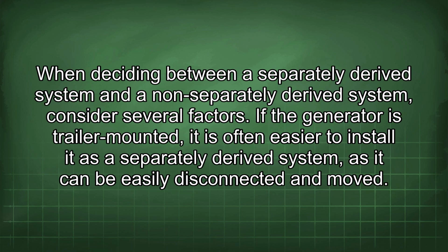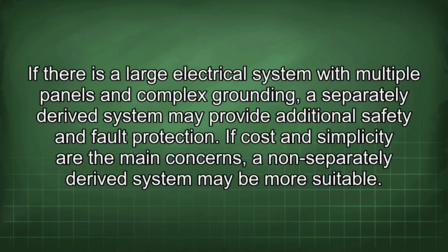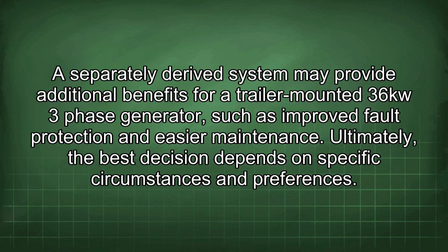When deciding between a separately derived system and a non-separately derived system, consider several factors. If the generator is trailer-mounted, it is often easier to install it as a separately derived system, as it can be easily disconnected and moved. If there is a large electrical system with multiple panels and complex grounding, a separately derived system may provide additional safety and fault protection. If cost and simplicity are the main concerns, a non-separately derived system may be more suitable. A separately derived system may provide additional benefits for a trailer-mounted 36-kW three-phase generator, such as improved fault protection and easier maintenance. Ultimately, the best decision depends on specific circumstances and preferences.